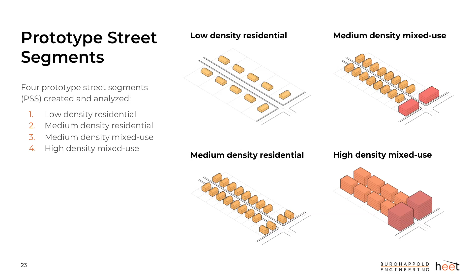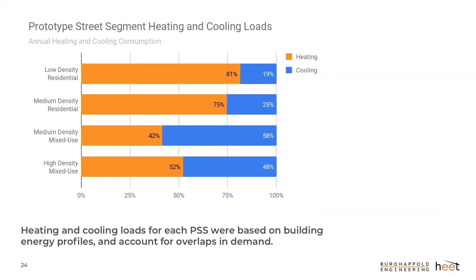For each of those prototype street segments, we applied building energy profiles to each building, then combined them in a way to account for coincident demand. So if one building is using heating and another is using cooling, they can cancel out. If they occur at different times of day, you don't have to size the system to the sum of all peak loads—you can lower it a bit. So we accounted for that.